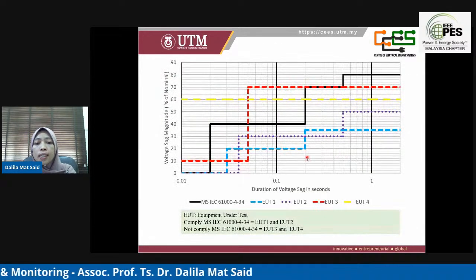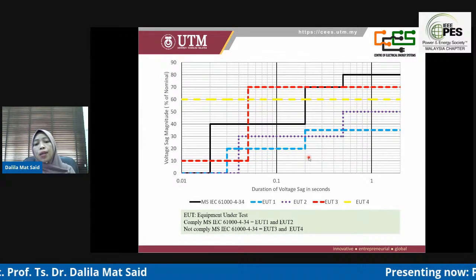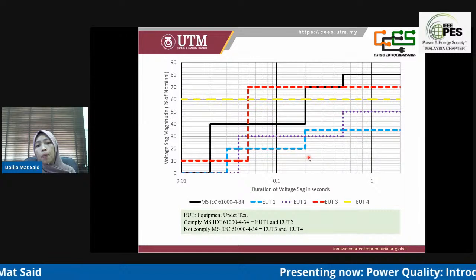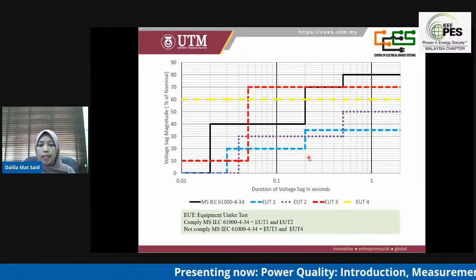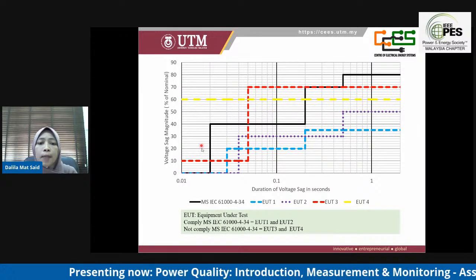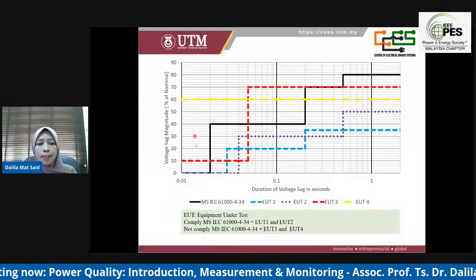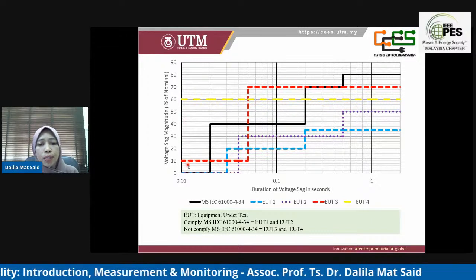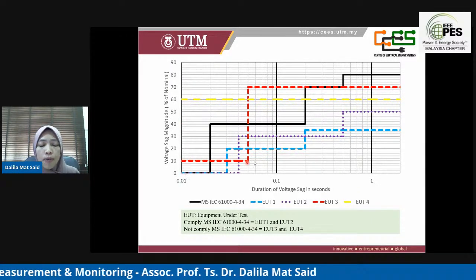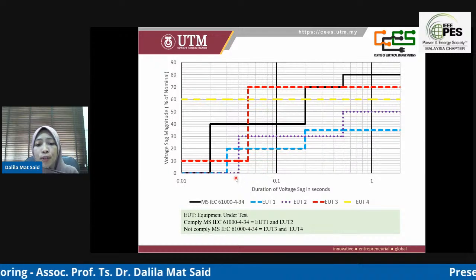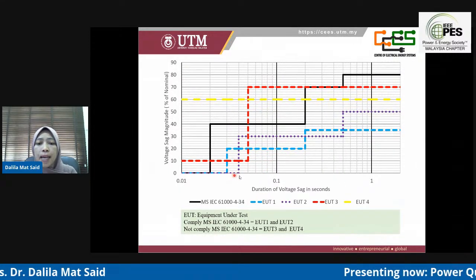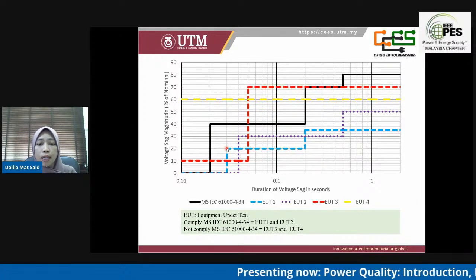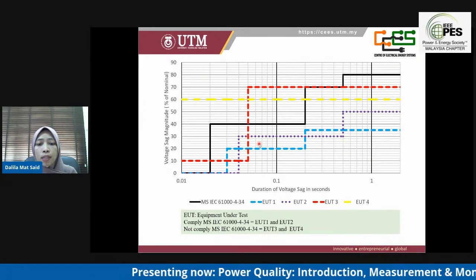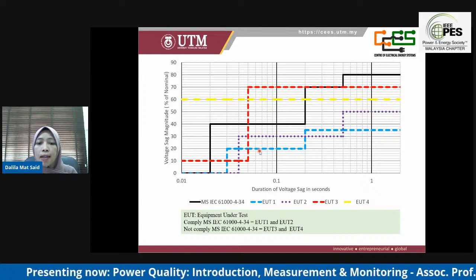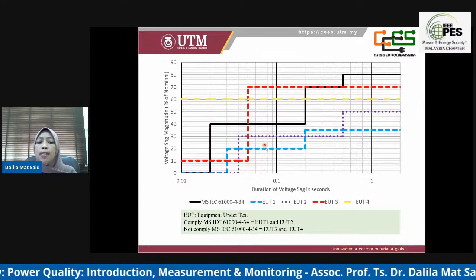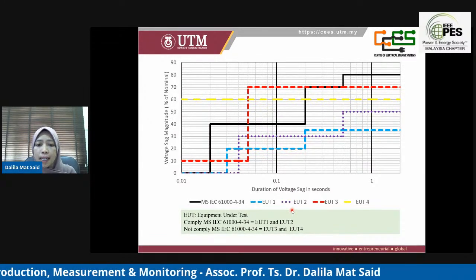So next, how do we apply this? I will show an example of the data plotted on the graph of the standard. From this graph, I will explain in detail. We have the voltage sag magnitude, which is the percent of the nominal value, versus the duration of the voltage sag in seconds. The black color in this graph is the MS-IEC 61000-4-34, and the remaining colors are EUT. EUT stands for equipment under test.